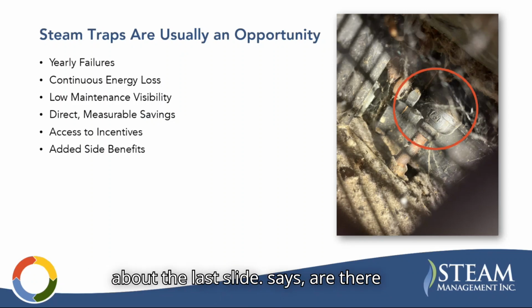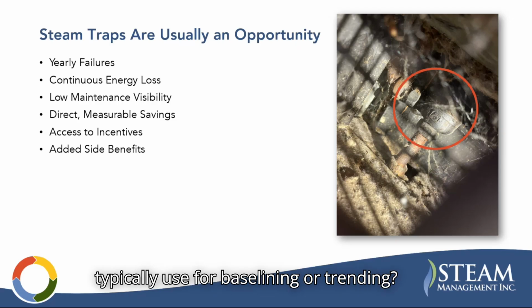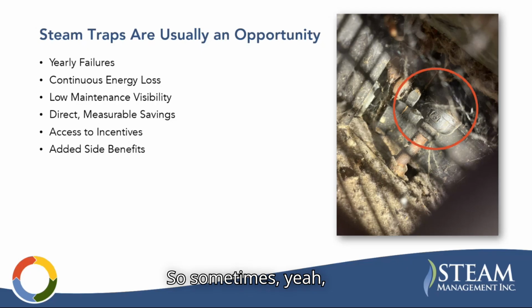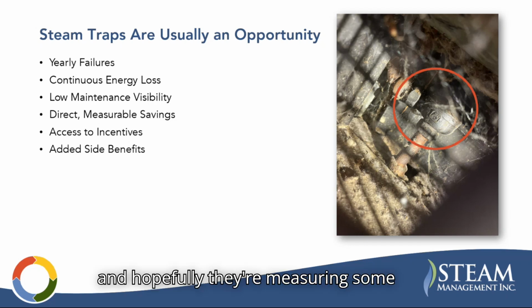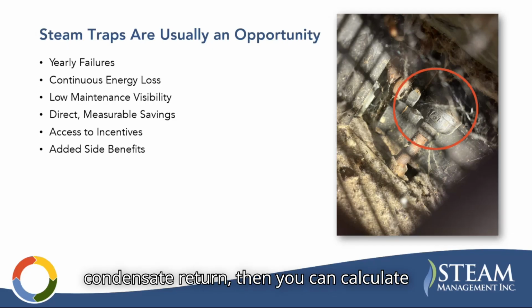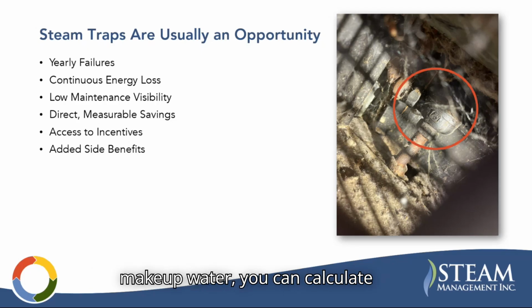So yeah, we have a question about the last slide. It says, are there any data logging equipment that you typically use for baselining or trending? So sometimes, yeah, a lot of times we're beholden to what the plant has. But luckily, I'll talk about a heat and mass balance later, where you can model out what the system looks like and use utility bills to get a good picture of the system. And hopefully they're measuring some stuff, right? If you have steam flow and they're measuring condensate return, then you can calculate makeup water. Or if they're measuring makeup water, you can calculate condensate return.